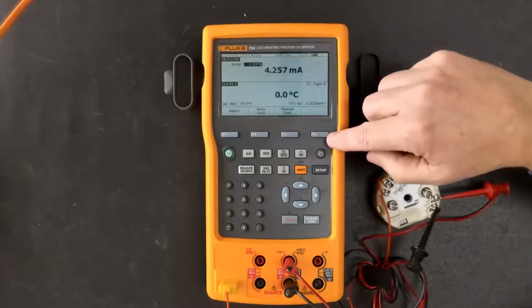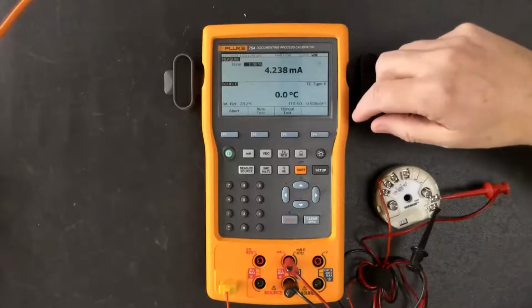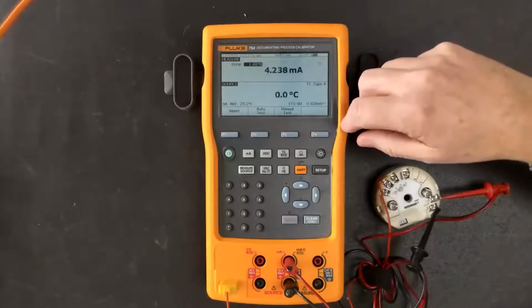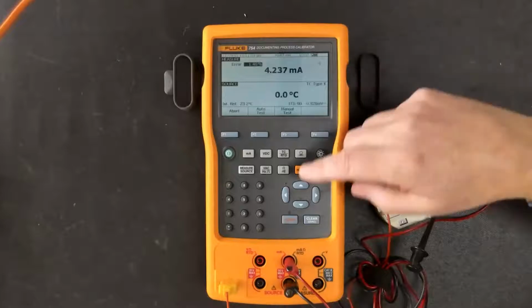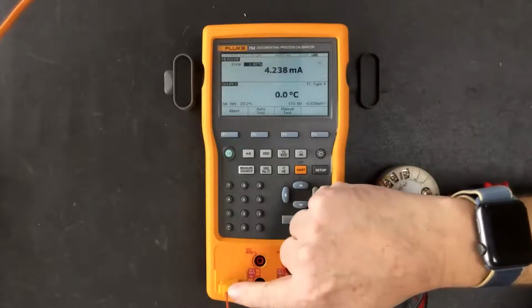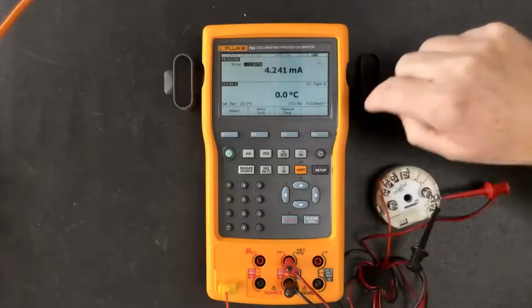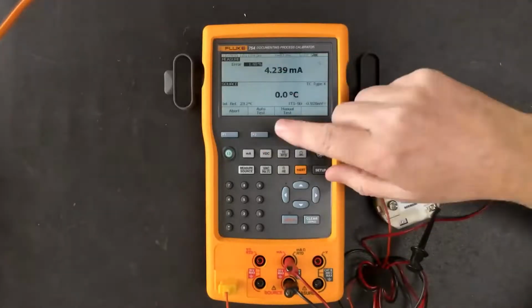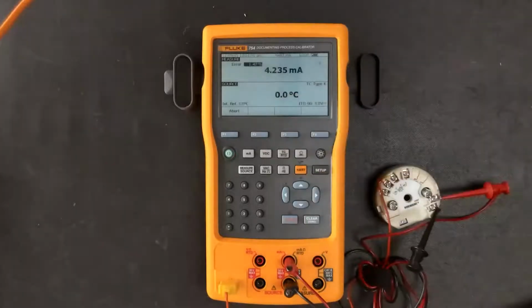Okay. Now, here's the fun part. With this calibrator, we can automatically run tests without having to do any manual stuff. So this is going to automatically source the thermocouple signal and measure the 4-20 milliamp and go through each test point with that 10-second delay. So I'll hit Autotest, and we're going to test this guy out and see what it looks like. And again, this is a 5-point test, so it's going to check at 4 milliamps, then 25, 50, 75, 100%. And you see we're going to 75 now, then we'll go to the next step up.